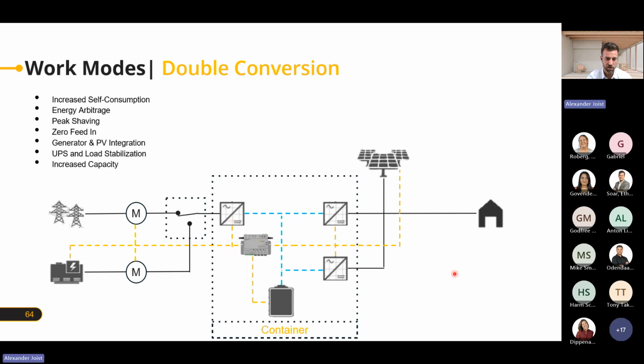Another work mode is double conversion with increased capacity. We could also increase the capacity if we do double output with only one input, but then we must make sure we have enough PV to support that. If there's not enough PV to support it and charge the battery, the system will collapse and won't deliver more power than what can actually come from the grid.